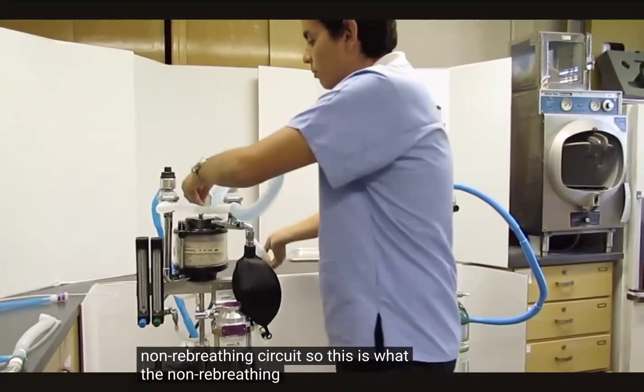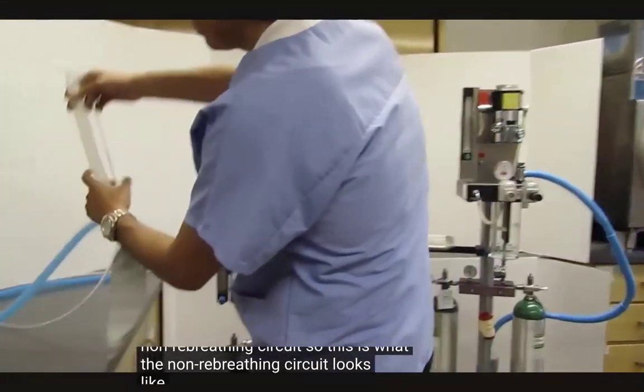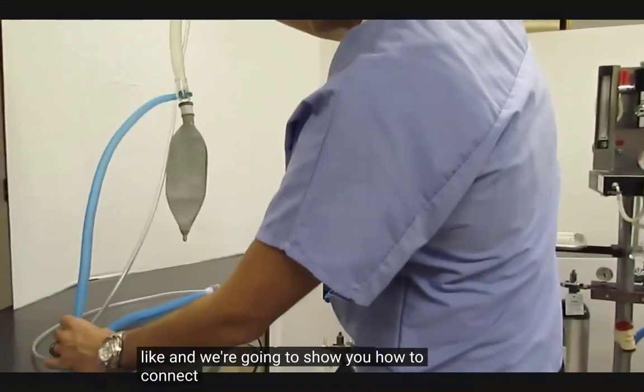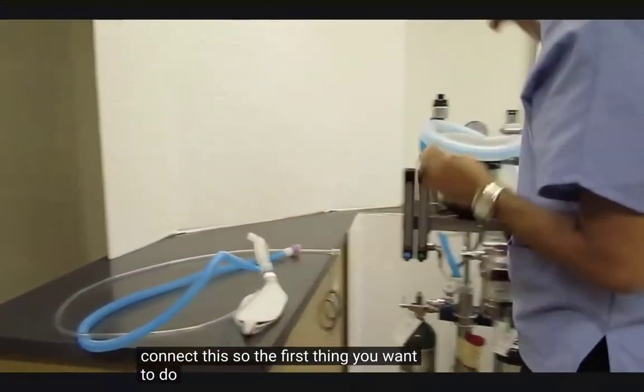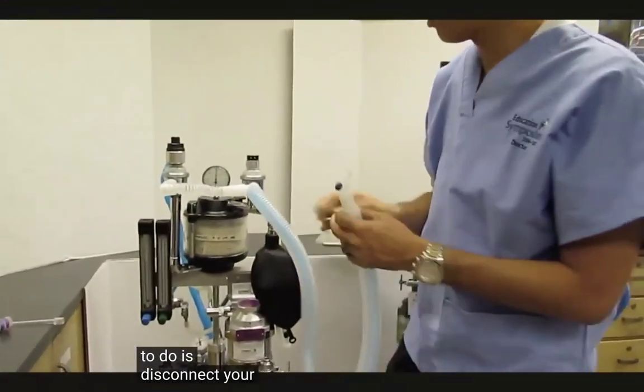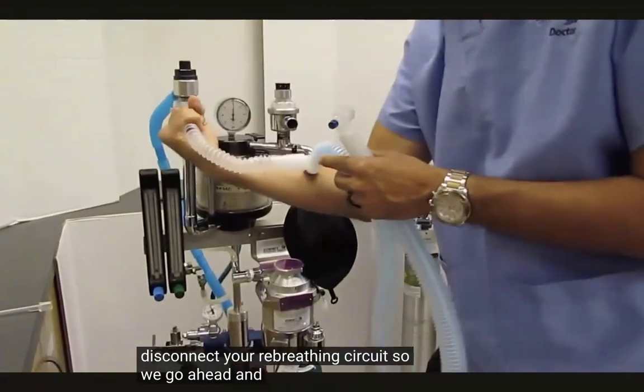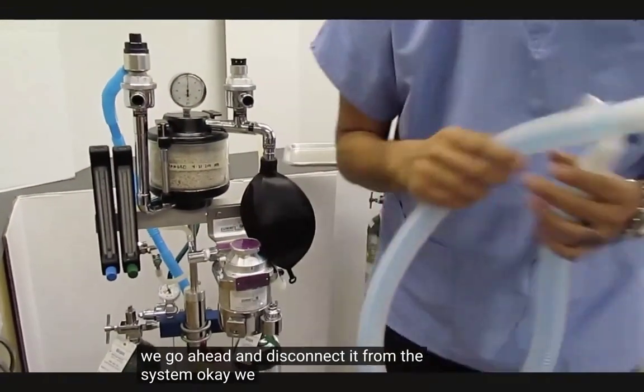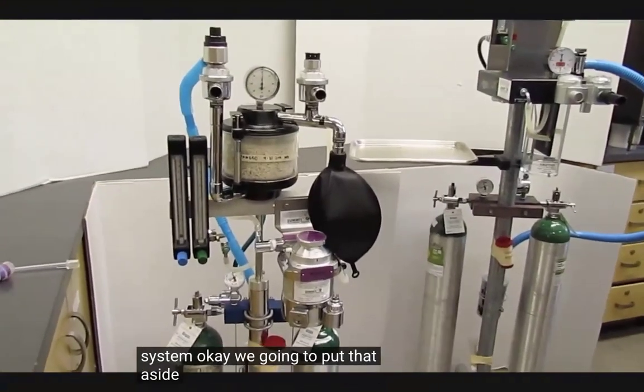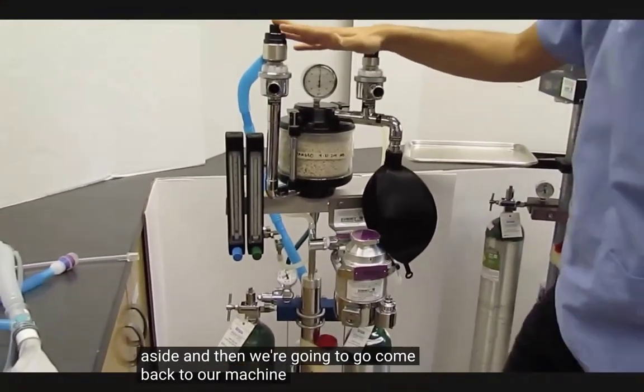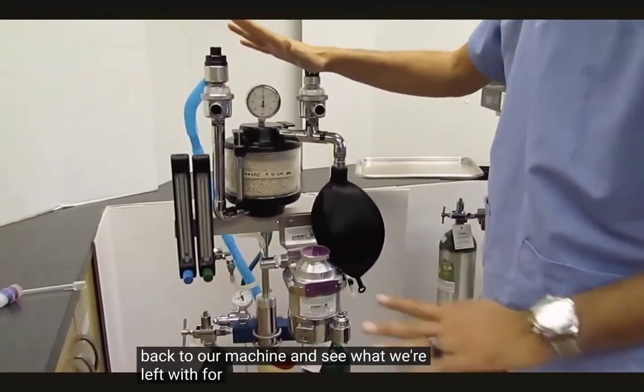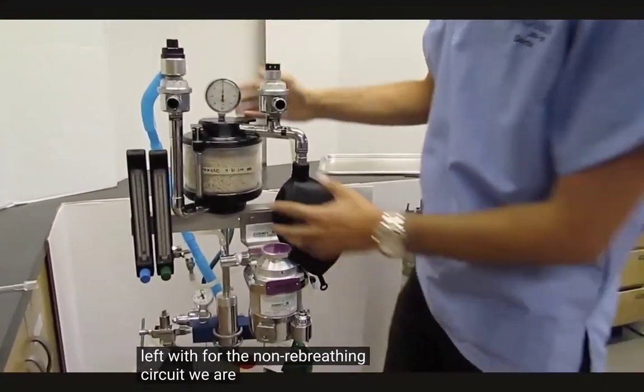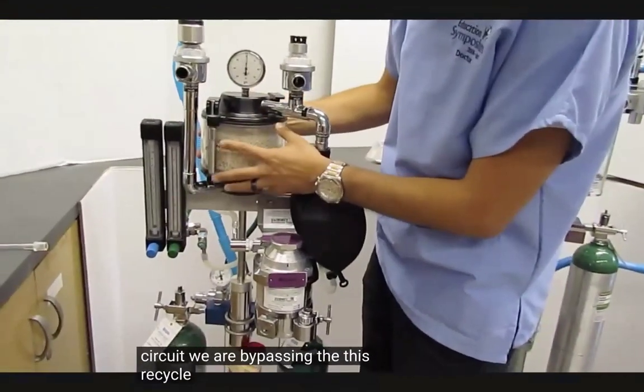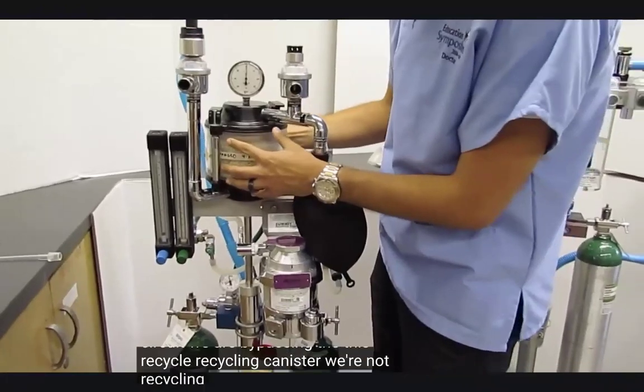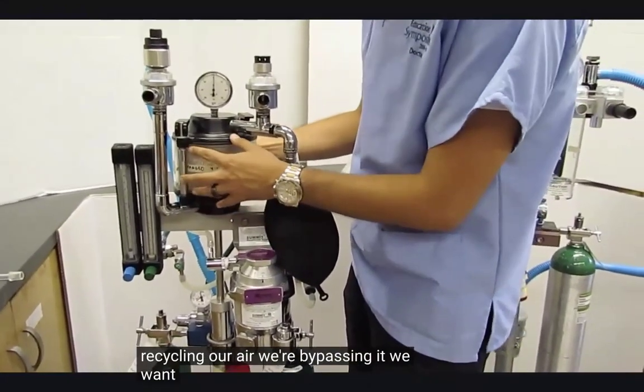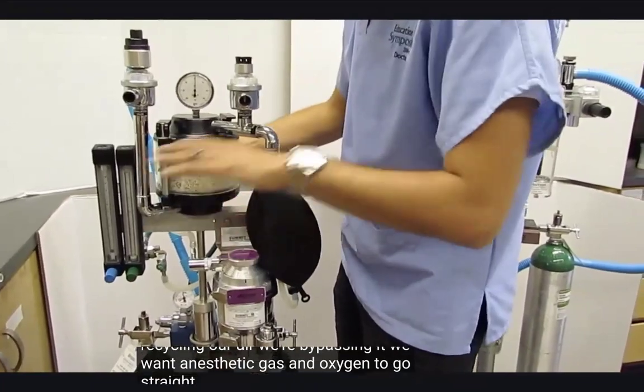So this is what the non-rebreathing circuit looks like, and we're going to show you how to connect this. The first thing you want to do is disconnect your rebreathing circuit. So we go ahead and disconnect it from the system. Okay, we're going to put that aside, and then we're going to come back to our machine and see what we're left with. For the non-rebreathing circuit, we are bypassing this recycling canister. We're not recycling our air, we're bypassing it. We want anesthetic gas and oxygen to go straight to our breathing circuit.